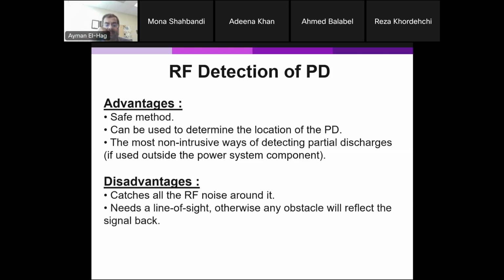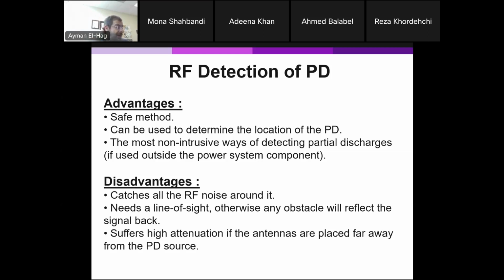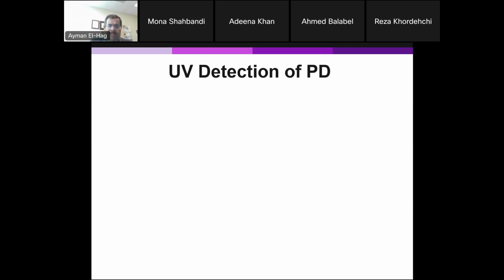Of course, it needs line of sight. If there's an obstacle between you and the object, it can't detect anything. And this is why I said if you are outside the transformer tank and there is a partial discharge inside the transformer tank, you won't be able to measure it. The antenna has to be inside. There has to be a line of sight between the antenna and the source of the partial discharge. It suffers from high attenuation, especially if your antenna is far away from the PD source. By the time it reaches you, it might be too small to be actually measured.